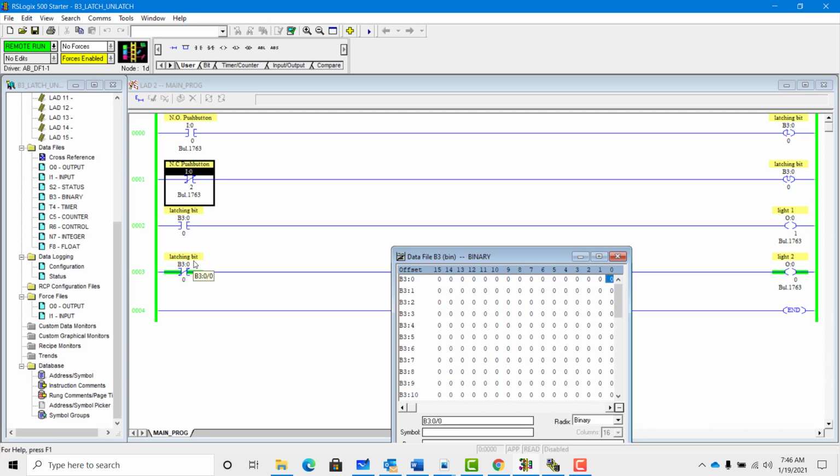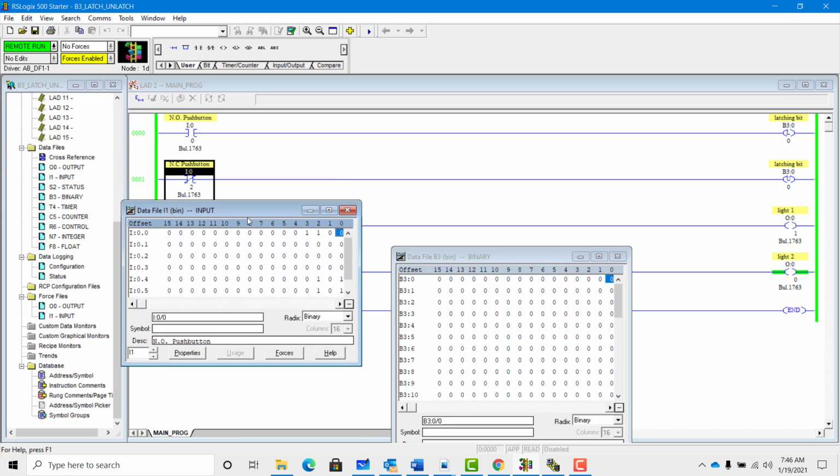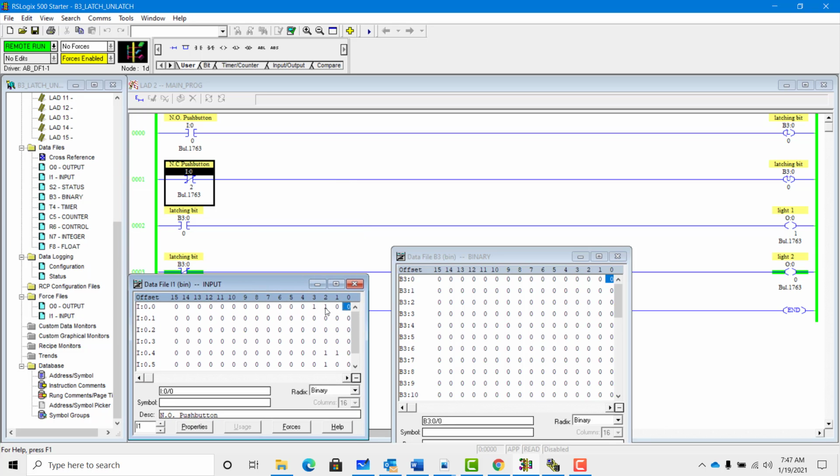This is a perfect example of not having electrical continuity to turn on an output. There is no electrical continuity right now in this program. So, well, actually I take that back. We do have electrical continuity through this switch. Input 02 is actually on, if we look at the input status file, input number 2 is on.